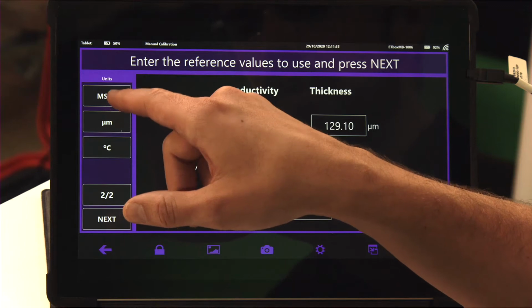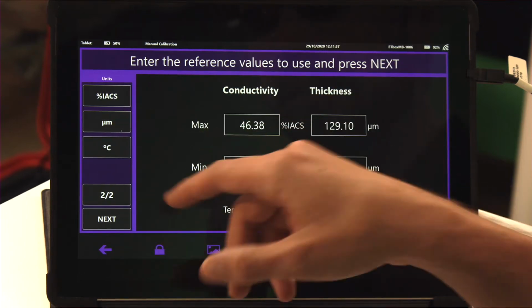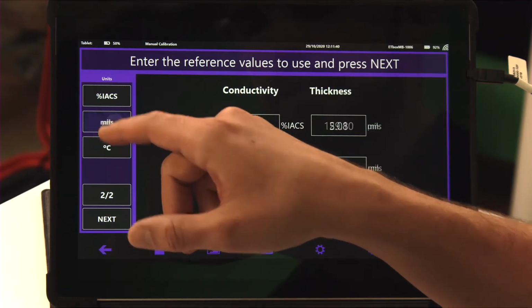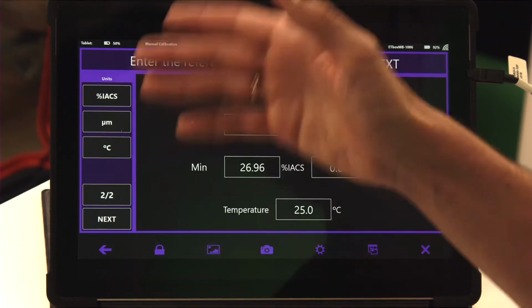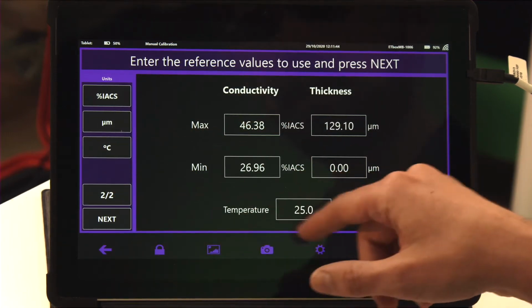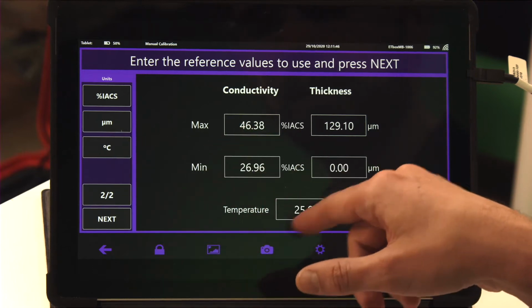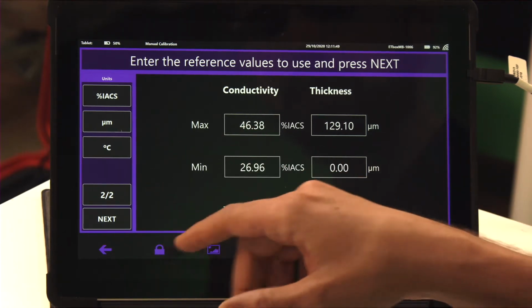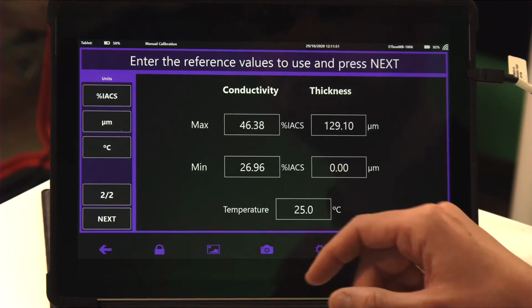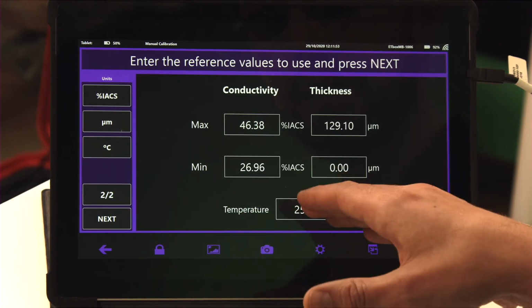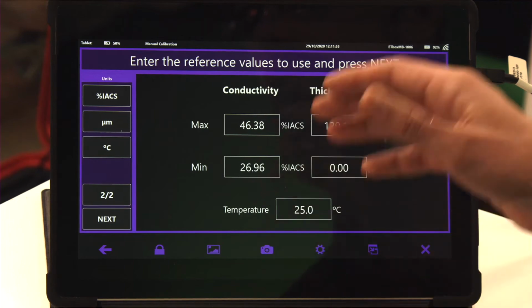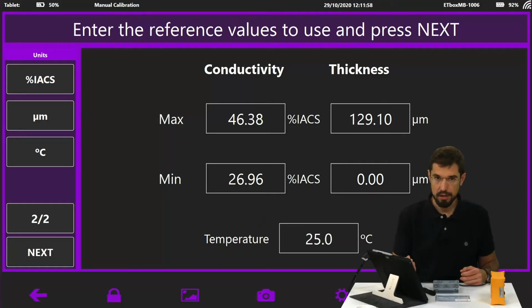We can go between megasiemens per meter or IACS, or between microns and inches. In this case, we're going to work with the international system. We can also choose the units in which our temperature will appear, either Celsius degrees or Fahrenheit degrees. It's important to introduce the test temperature since the algorithms are going to work with it to obtain better accuracy.